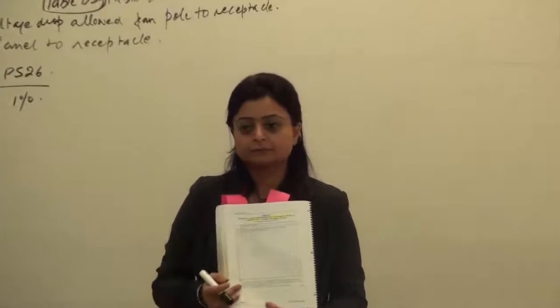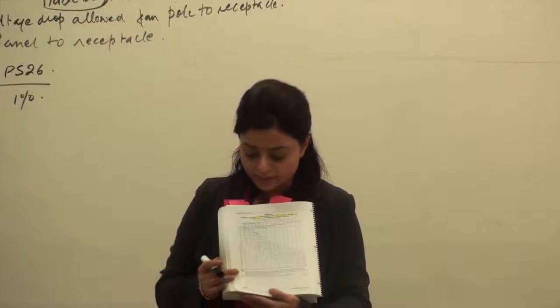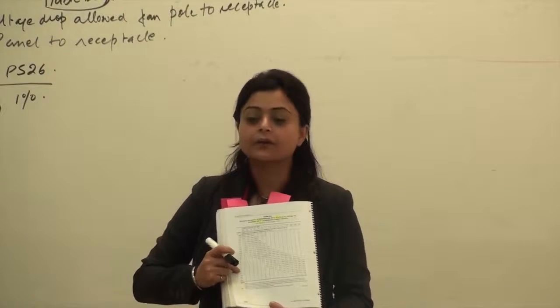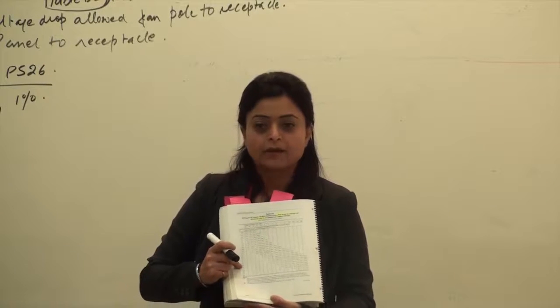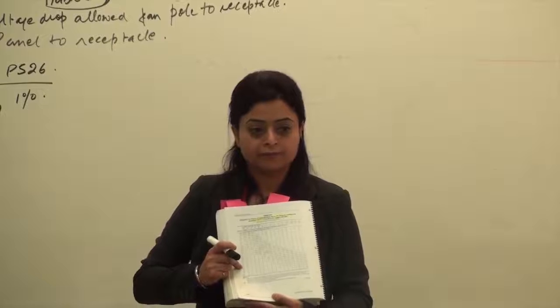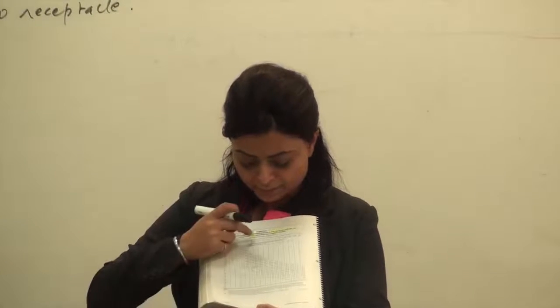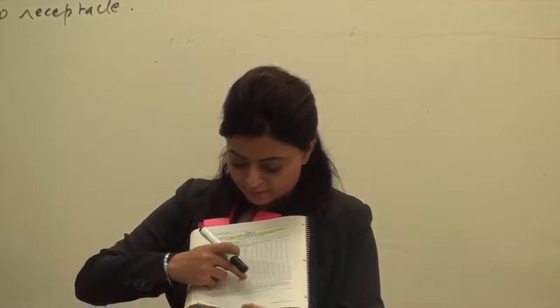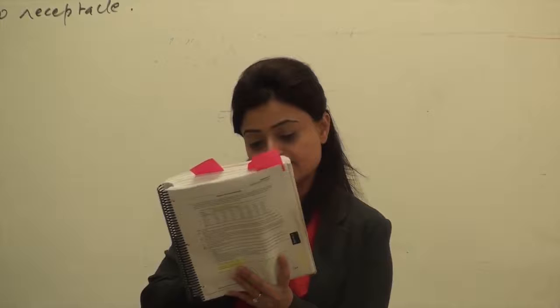So let's say in my home I'm working with 100 amps. So I will go to 100 amp here, okay. Let's say I'm using a conductor of size number 6. So I will go to 100 amp, keep going to number 6. For 100 amp, the allowed distance for number 6 is what? 6.2 meters.